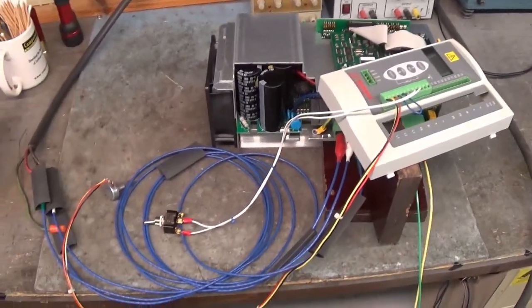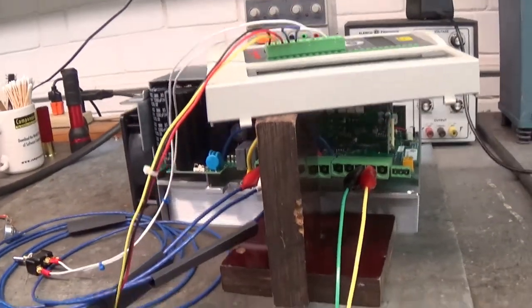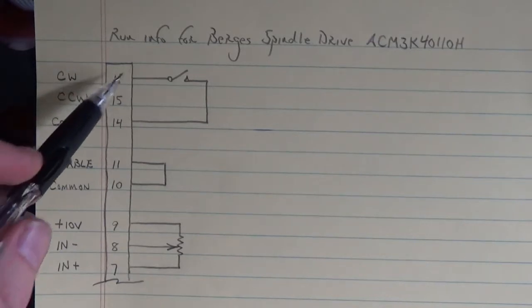At the end of the video I'll show you the hookups to make this drive go, so stay with us. Even though we've made it to the shop, here are the control connections on the Berges Spindle Drive ACM3K40110H. On terminals 16, 15, and 14, we have clockwise direction, counterclockwise direction, and common.